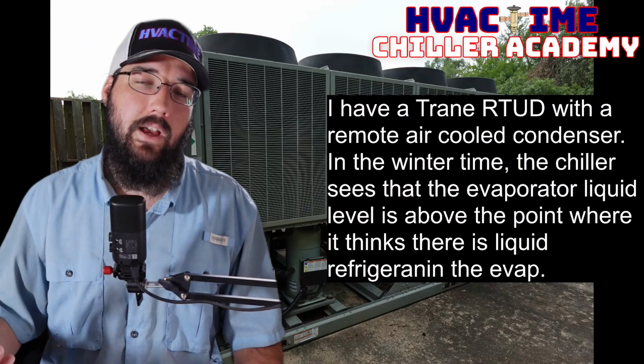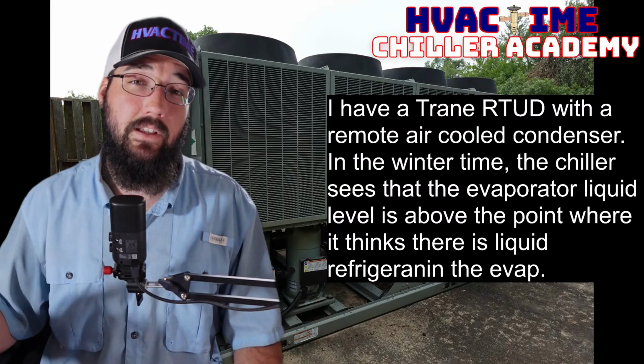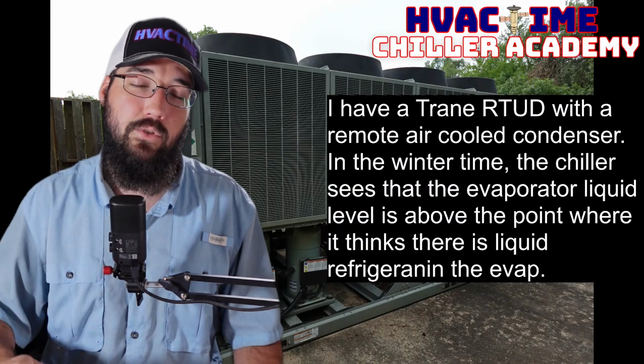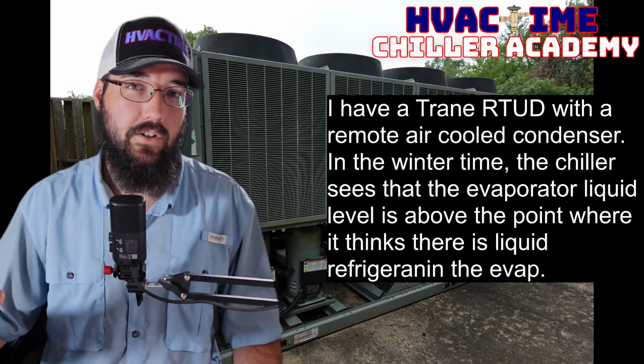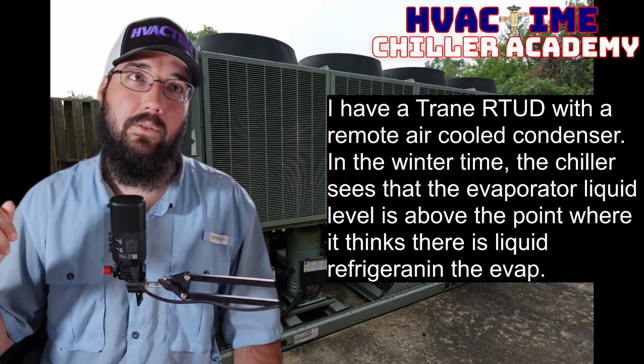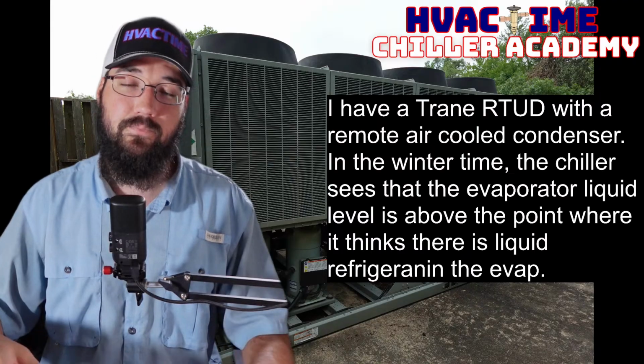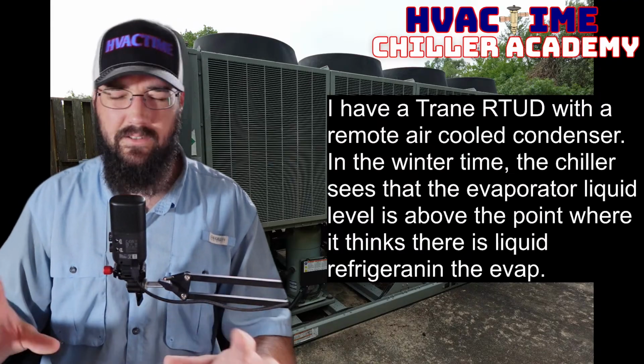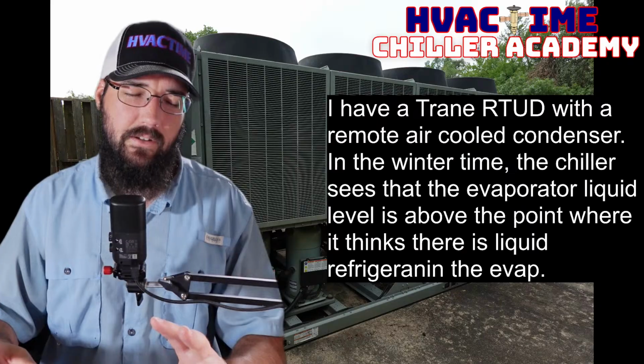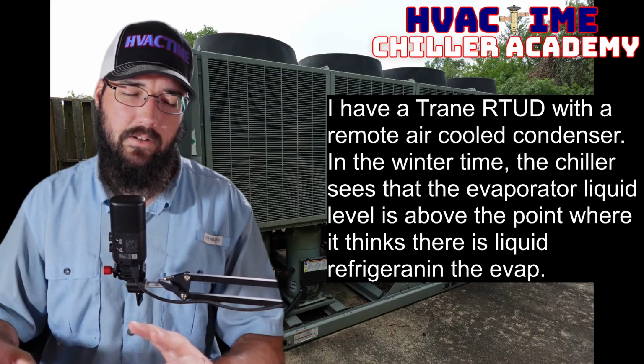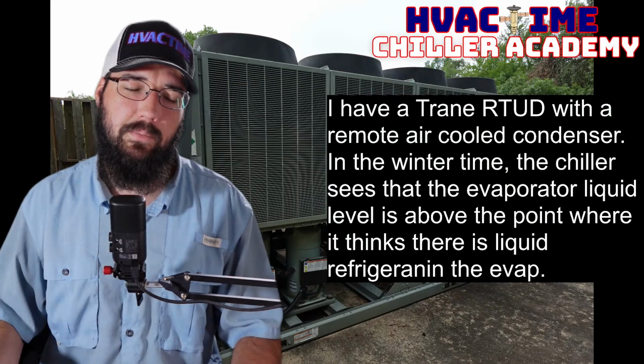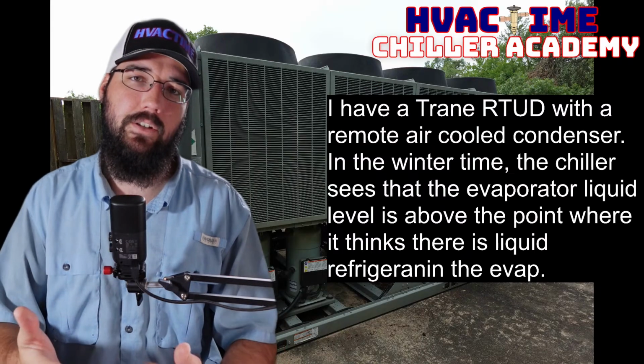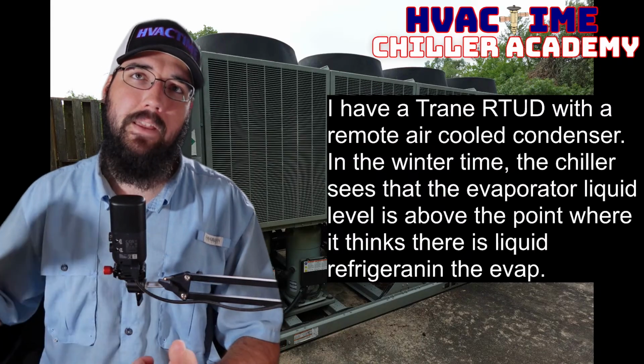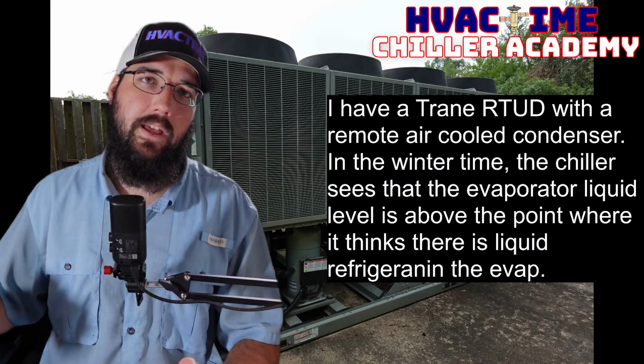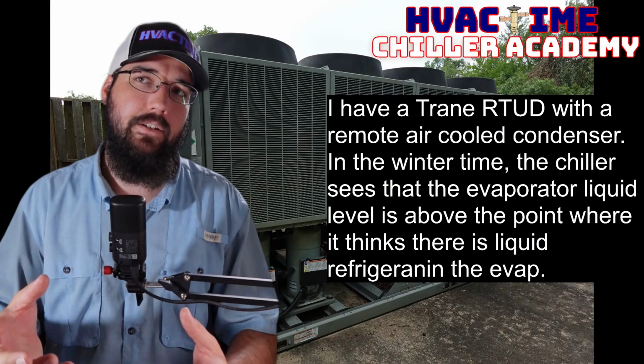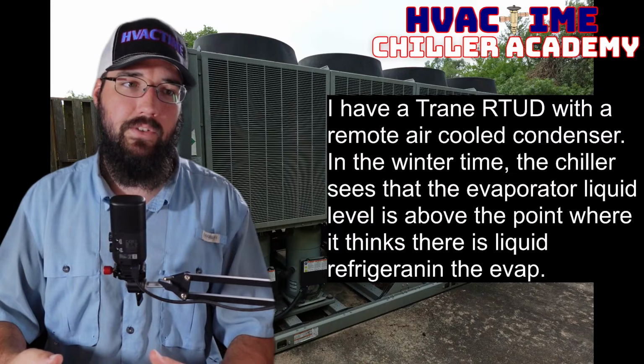One of the ways I look for if that check valve is leaking is when it does engage the gas pump, do I see a sudden spike in suction pressure and discharge superheat? Discharge superheat may be a little less useful, but especially the suction pressure. Is there a sudden spike in that pressure? And if there is, then that's where I'm looking at that check valve.